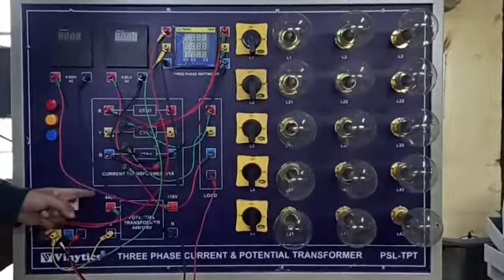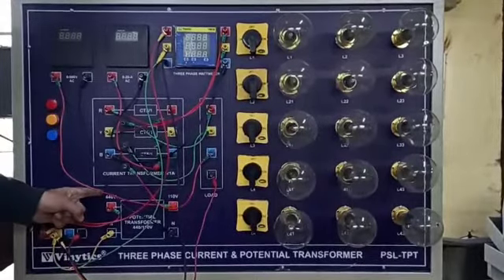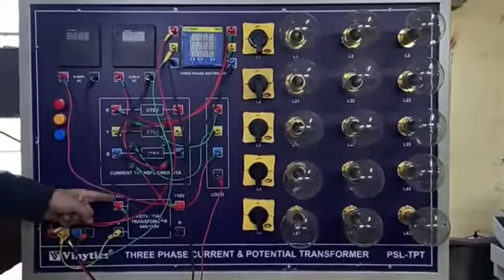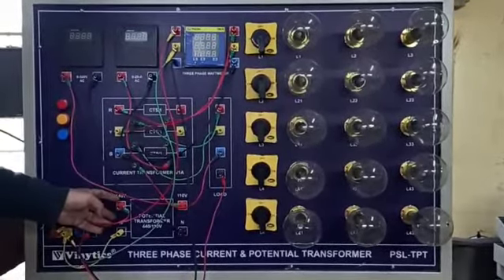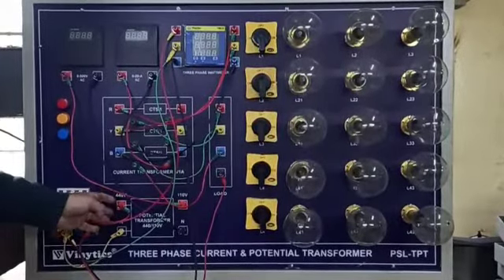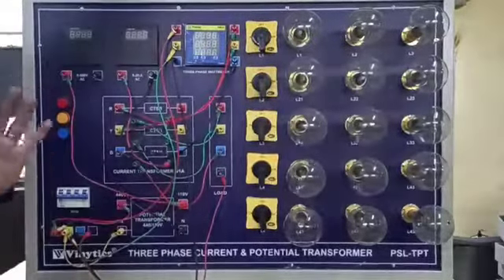This potential transformer has a ratio of 1 is to 4. That is 440 volt input, 110 output. Basically what it does is, any voltage that you will give here, it will give divided by 4 here.